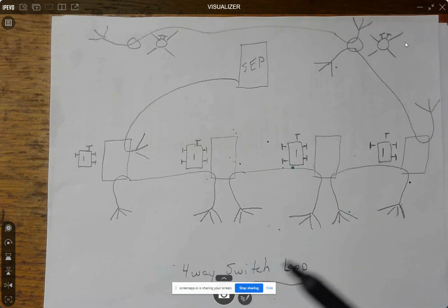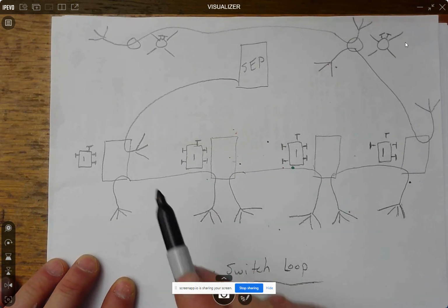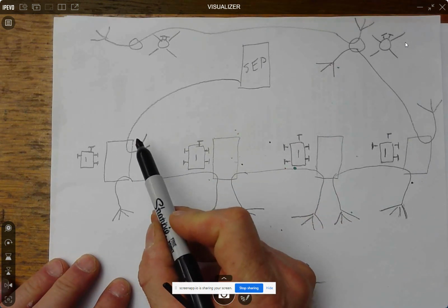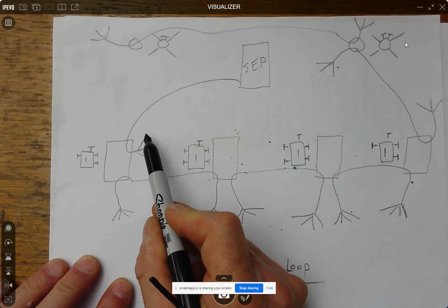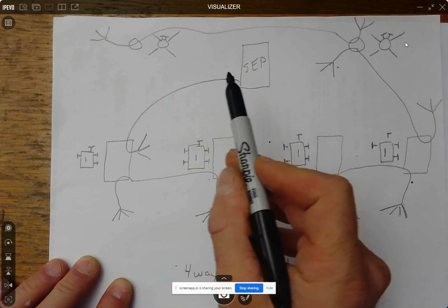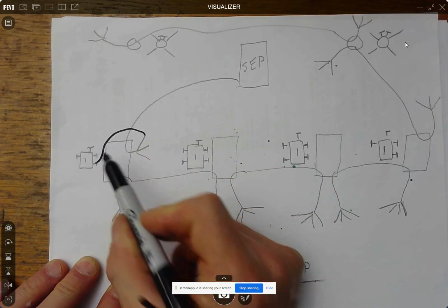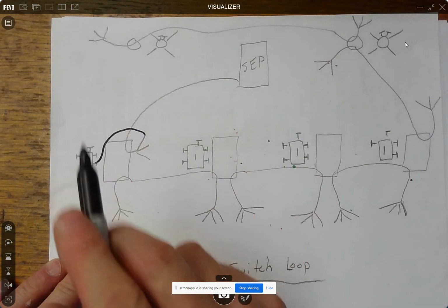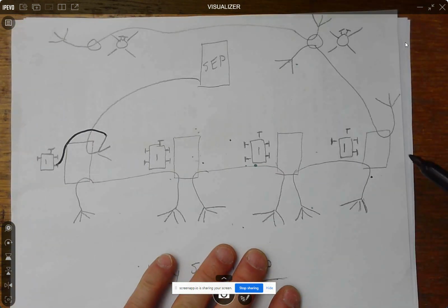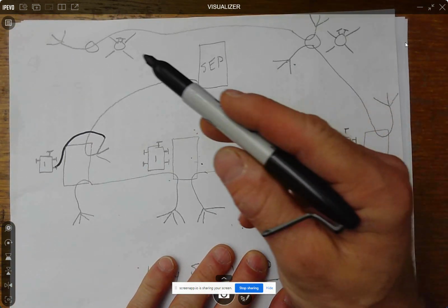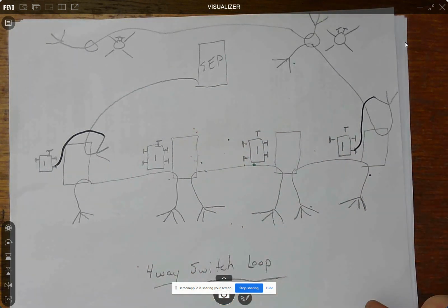Anyway, in a three-way or four-way switch circuit, also called switch loops sometimes, the first thing you're going to do is take your incoming power. I have black in my hand here, so the black is my incoming power. There's going to be a black insulated wire in this cable, and we're going to draw it from here to our common terminal. That is our power coming into this entire switch circuit. All the electricity comes in on that one wire. Then over here, the wire is going to go out to what we're powering, these lights, and that's going to come in right there.